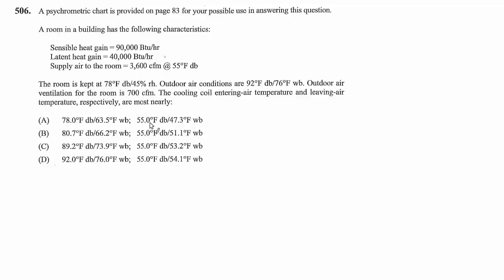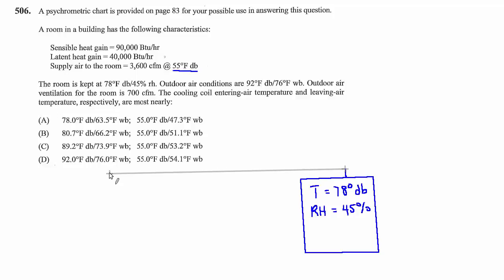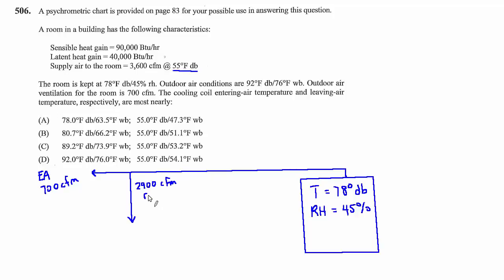In all cases the leaving coil temperature is 55 degrees, as that was given. To work through this, let's draw a picture of the scheme. The conditions in the room are 78 degrees dry bulb and 45% relative humidity. There's extract from the room because 700 CFM of fresh air is being introduced, so there must be exhaust air of the same volume — 700 CFM. The remainder gets recirculated: 2,900 CFM of recirculated air. Outside air being introduced is 92 degrees dry bulb, 76 degrees wet bulb.